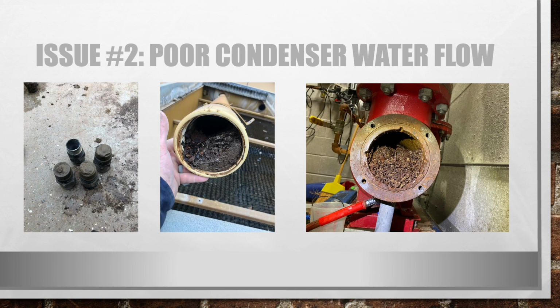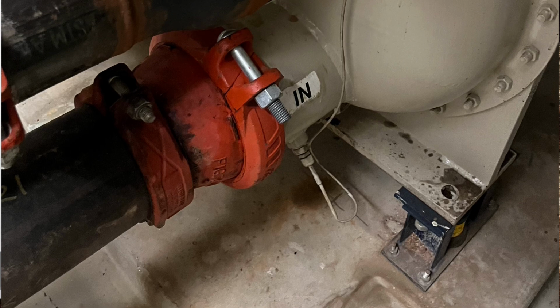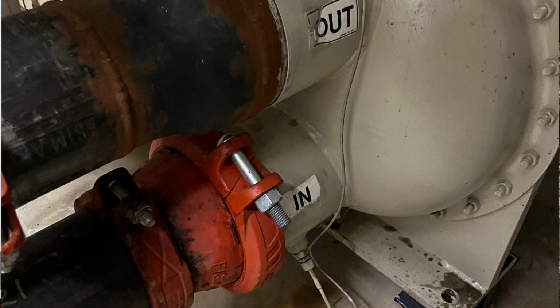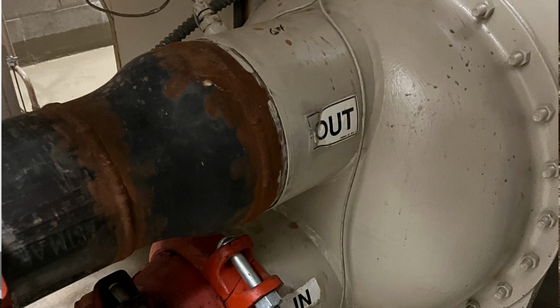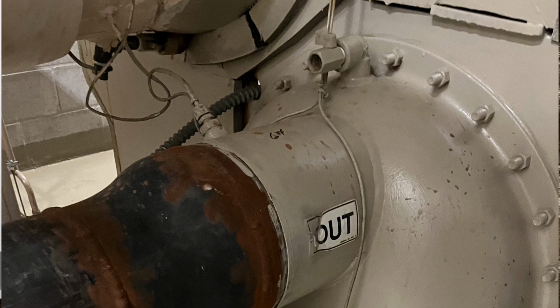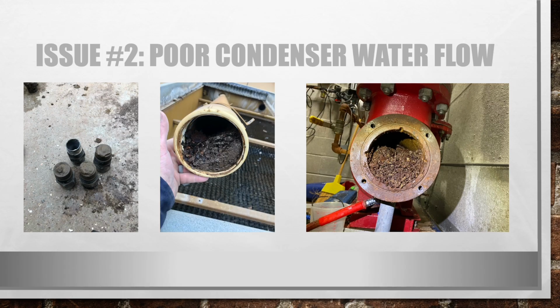If that stuff's clean and you still think you have a condenser water flow problem, then go ahead and pull the piping side of the condenser and check that out. See if there's any rust buildup in there or any debris that got lodged in there that could be blocking the flow. I'll have some more videos coming out as well on diagnosing condenser flow, but this should get you started. It's pretty self-explanatory. Most of the time it's a plugged screen. Most of the time it's plugged nozzles or something like that. Those are the most common things I've seen.